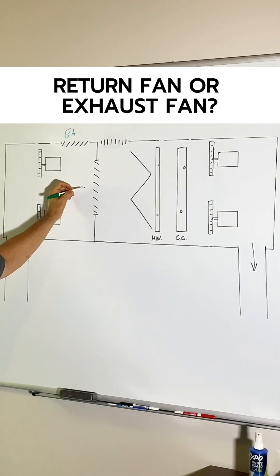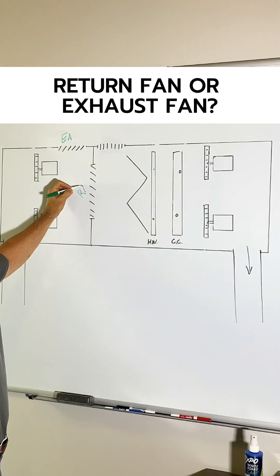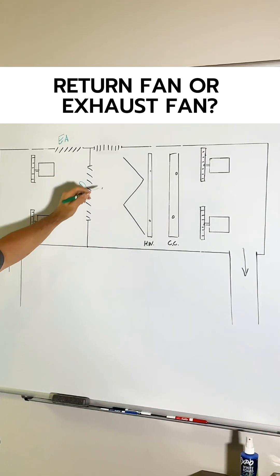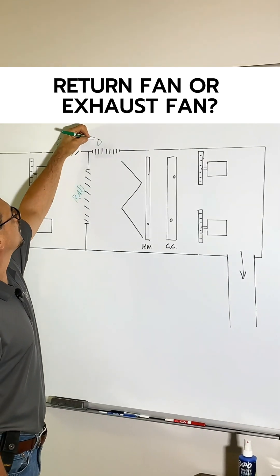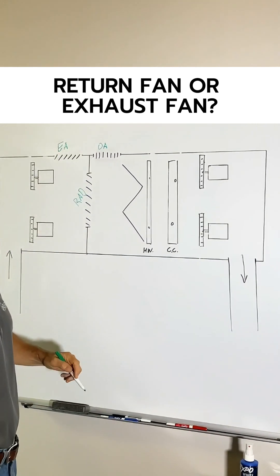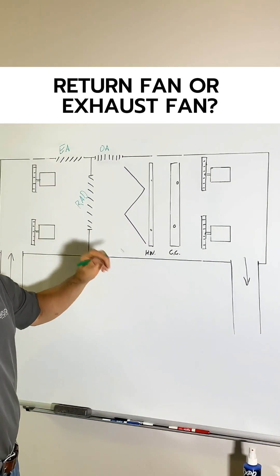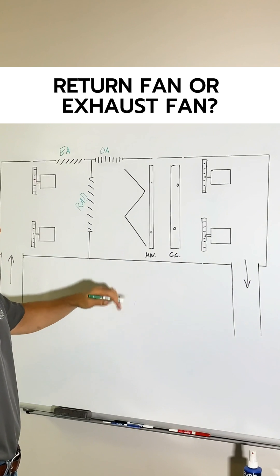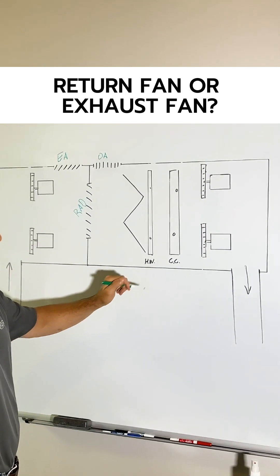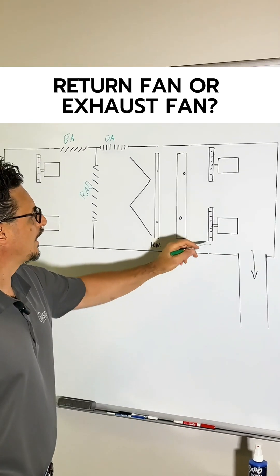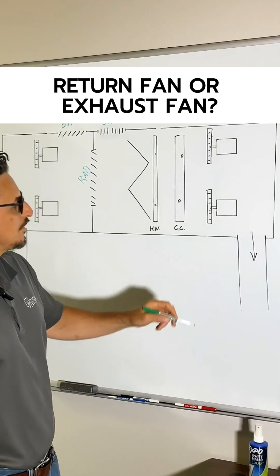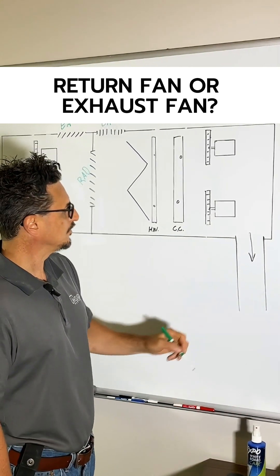This would be your return air damper, we'll call that a RAD, and this would be your outdoor air damper here. Pre-filter, obviously that could be a filter bank with bigger filters. Hot water pre-heat coil. Chill water cooling coil, and then your two supply fans and your supply fan plenum going out to the building.